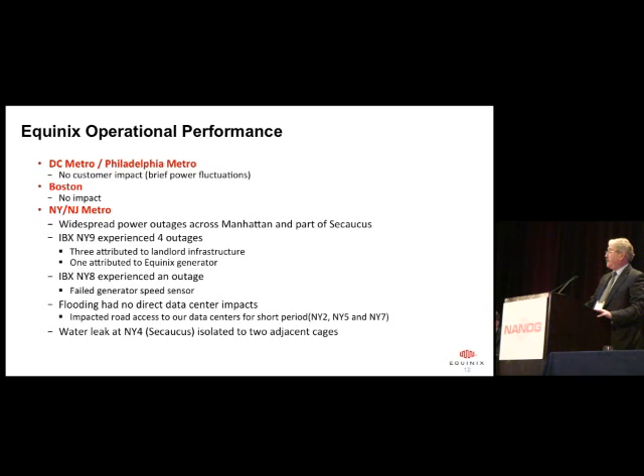The landlord's generators failed, and that was a major issue. One of our generators also failed due to fuel supply. At 111 8th, everybody gets fuel from the main building tanks, which belong to the landlord, and that was another issue, debris stuck in the pipe. So it was our generator, and it just went down.